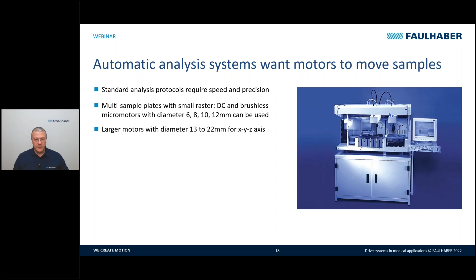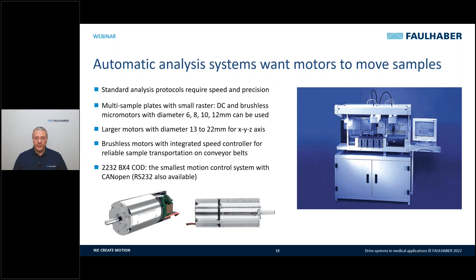This is an 8 millimeter brushless motor with a gearhead. Larger motors can be used for the movement of larger sample heads, typically 13 to 22 millimeters for the axis. We also have an option for lead screws, for example, in order to make linear movement in an easy way. Brushless motors with integrated speed and motion controllers can also be used for a very compact solution with RS-232 or CANopen communication systems.